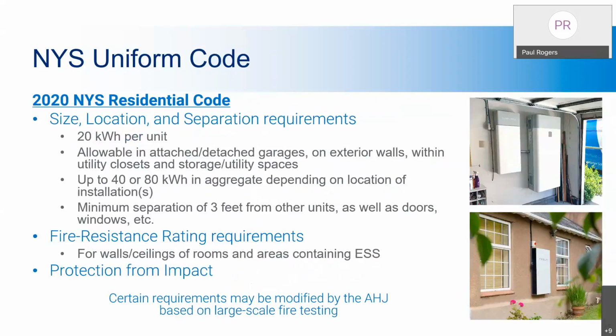So back to the uniform code and the residential code. In the 2020 New York State residential code, they looked at the size and separation requirements for these energy storage systems that go inside. As you can see in the picture on the right-hand side, it's installed inside a garage, and there are certain criteria if you're going to put it there. But anytime you go on the interior, the highest amount of energy you can put in is 40 kilowatt hours. No unit could be more than 20 kilowatt hours per unit. The highest you could have inside the dwelling or the building itself, when you're dealing with a private dwelling or the residential code, is 40 kilowatt hours. When you get to the outside, you can put up to 80 kilowatt hours, and you must just follow the prescriptive code in order to do that.